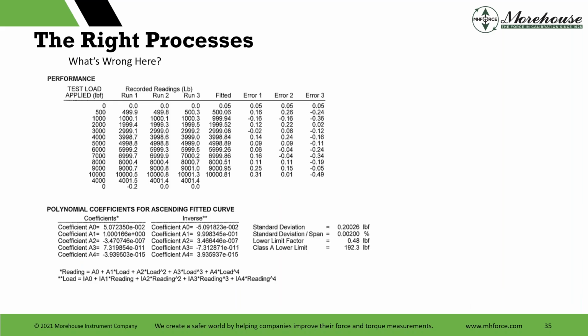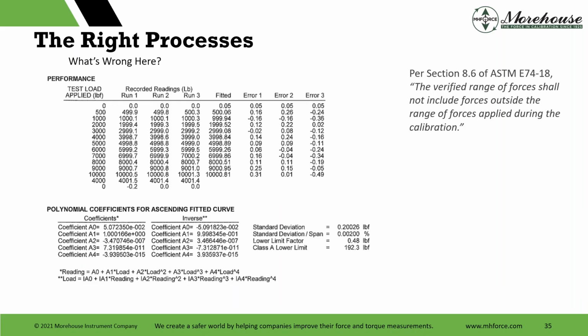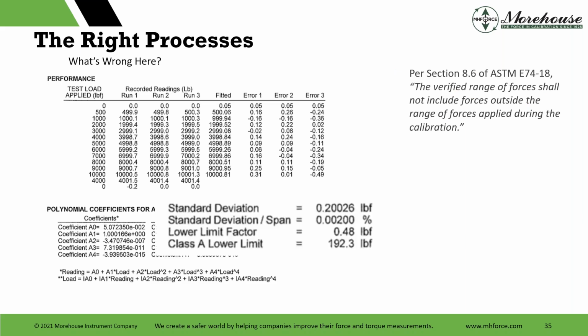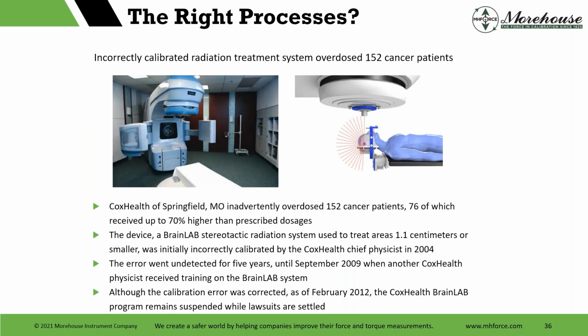Other examples of processes, here's an example of ASTM E74, a calibration provider not following the standard. It says the verified range of forces shall not include forces outside of the range of calibration, and that the range of calibration gets defined as 400 times the resolution, and it's non-zero force. So really, the range for this person, to clarify for everybody looking at this, they're saying it's good from 192.3. According to the standard, it's only good from 500 pounds onward. But not knowing.